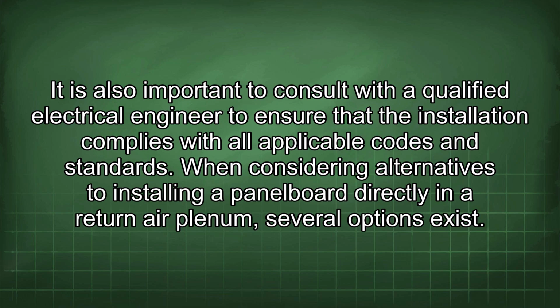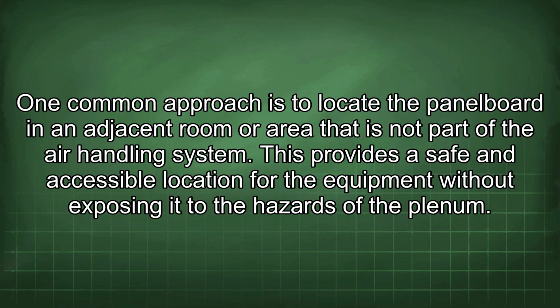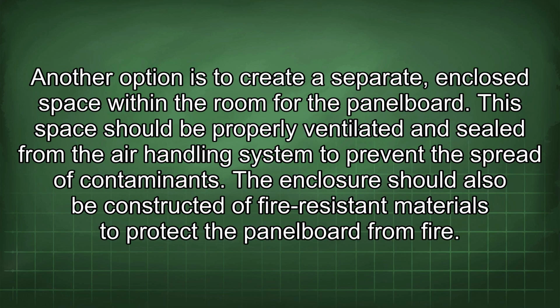codes and standards. When considering alternatives to installing a panelboard directly in a return air plenum, several options exist. One common approach is to locate the panelboard in an adjacent room or area that is not part of the air handling system. This provides a safe and accessible location for the equipment without exposing it to the hazards of the plenum. Another option is to create a separate, enclosed space within the room for the panelboard. This space should be properly ventilated and sealed from the air handling system to prevent the spread of contaminants. The enclosure should also be constructed of fire-resistant materials to protect the panelboard from fire.